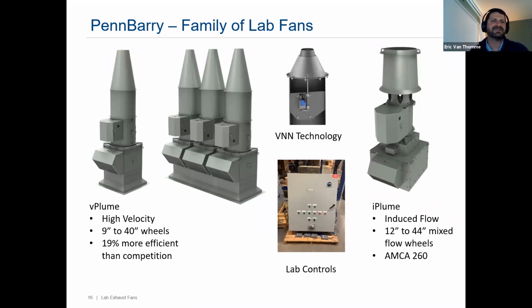This is a slide that kind of rounds out our entire family of lab fans. As I mentioned before, we have our V-Plume. This is our high velocity style, up to 40-inch diameter wheels. Most of our testing is showing 15 to 20% more efficient than our competition. We also go over to our AMCA 260 certified induced flow fan. We offer this in a belt drive or direct drive configuration up to 44-inch diameter. And then two ancillary controls features that I mentioned that give you greater flexibility for staging and energy control are the variable nozzle technology that I mentioned on the previous slide, as well as some lab exhaust fan controls. These are all available through Pennbarry.